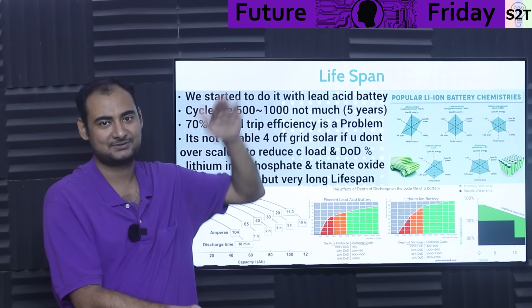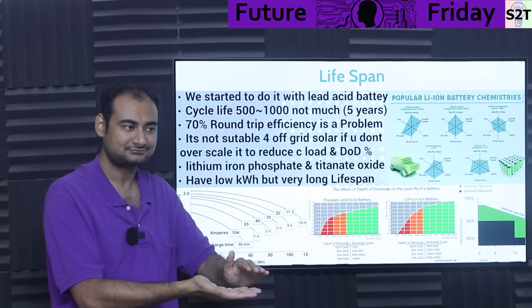I thought, why not go to sodium and all that? Sodium has two problems. First, it's not ready for prime time, because the voltage drops so low that your amp rating goes crazy on the DC bus. Even though the chemistry can go from 100% to 0%, by the time it reaches as low as 50%, the voltage drops so low that your inverter circuit says it can't go that low. So it's difficult—that technology isn't there yet.